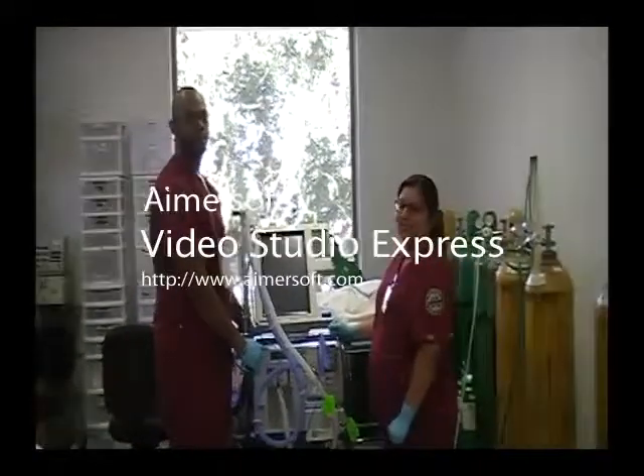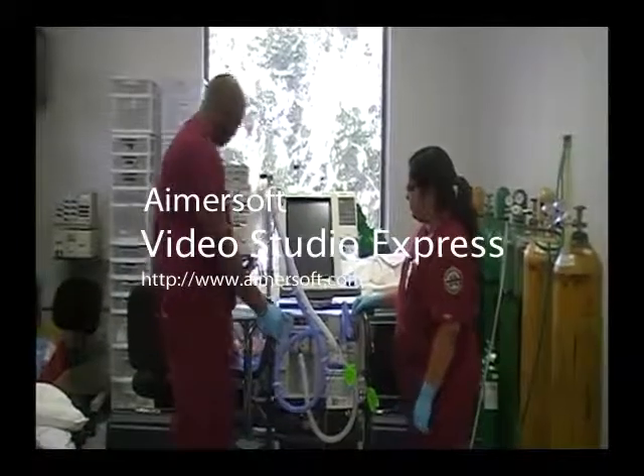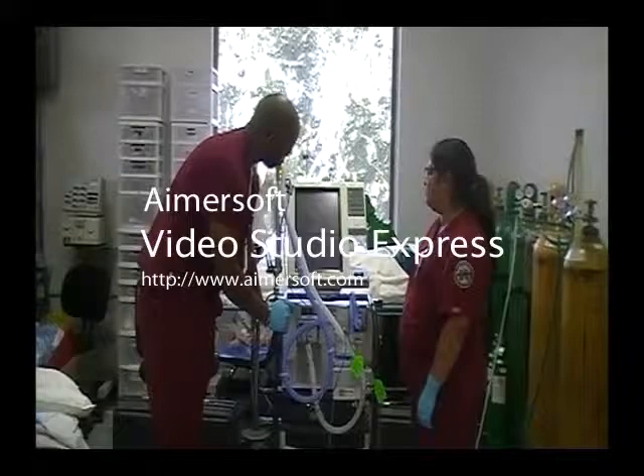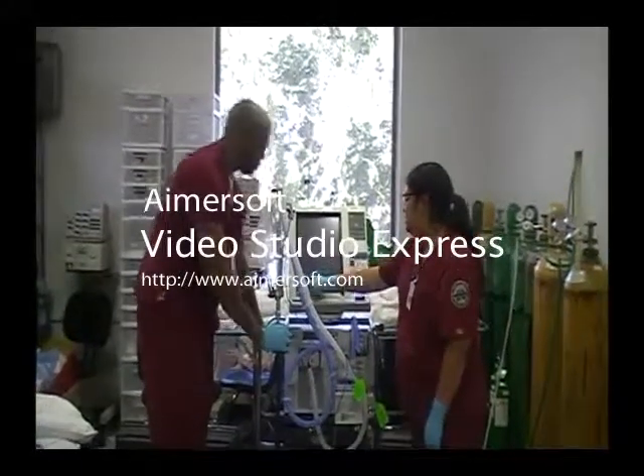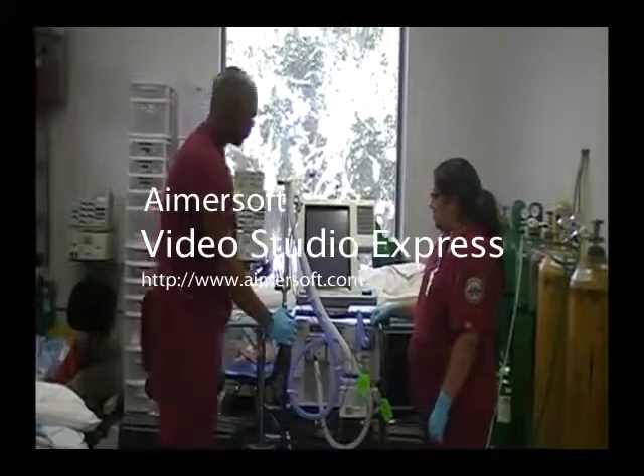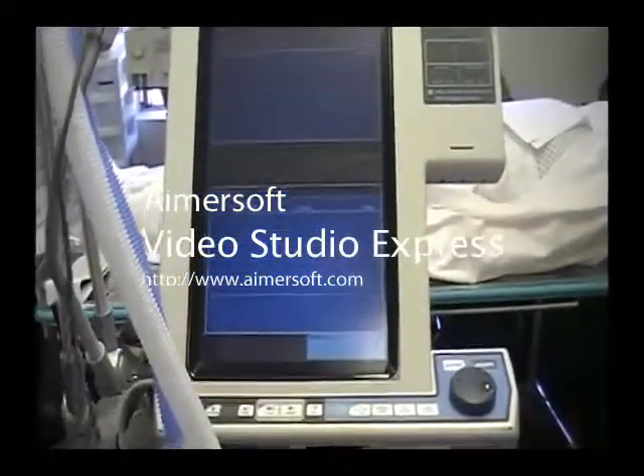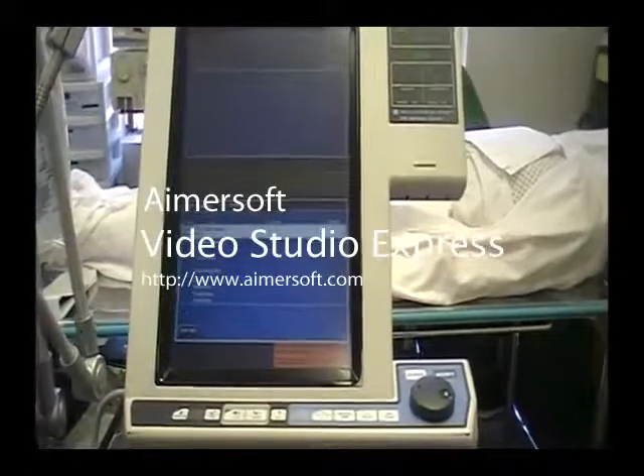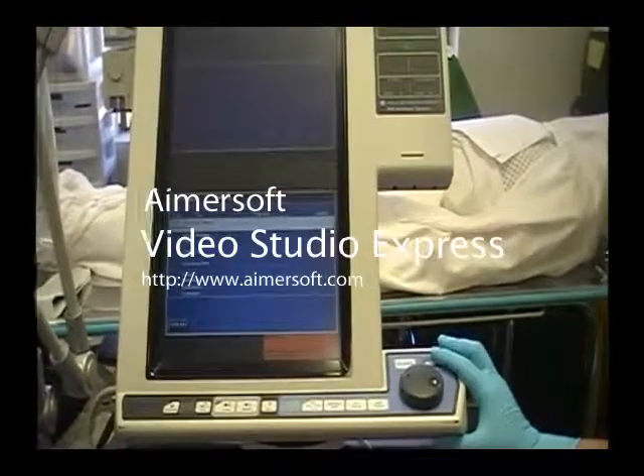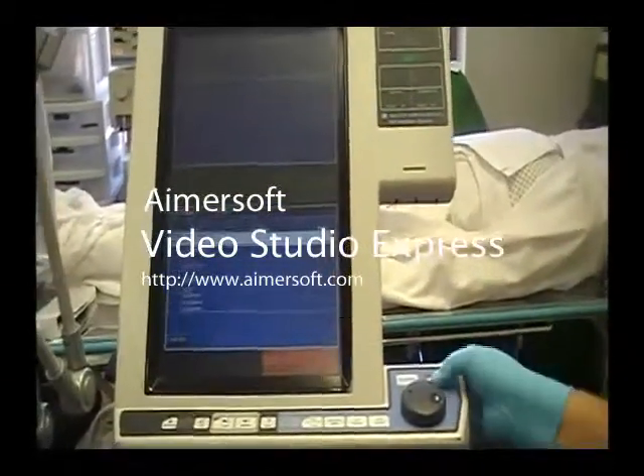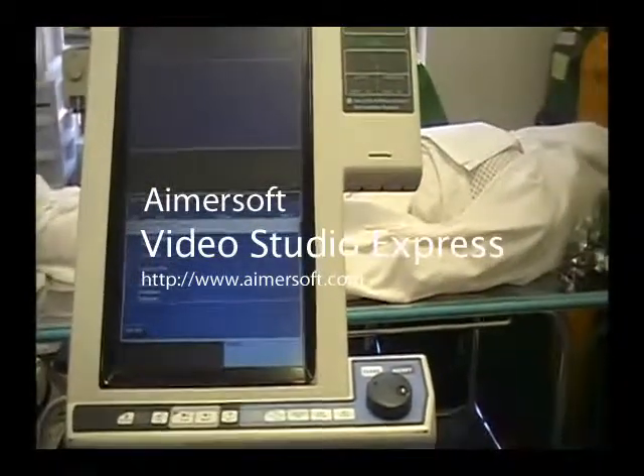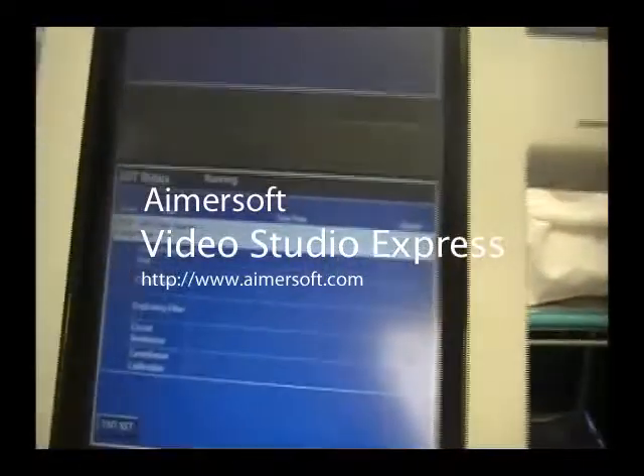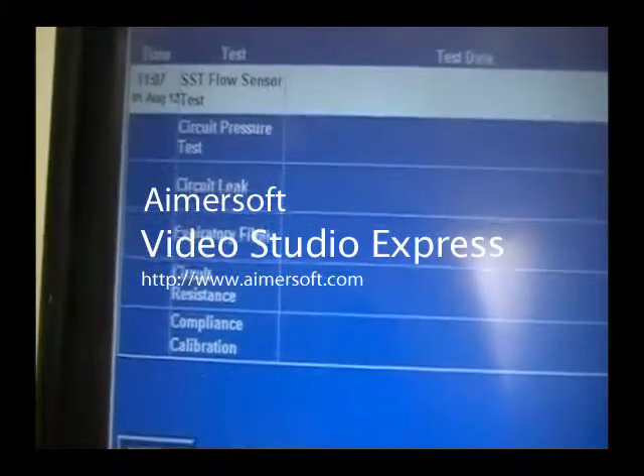So now we're going to test the equipment for proper function. Turn on the ventilator. Push the SST to test. We're selecting heated wire, adult patient, accept. And these are the things that the vent is testing: the flow, the circuit pressure, the leak, the expiratory filter, the circuit resistance, and the compliance.